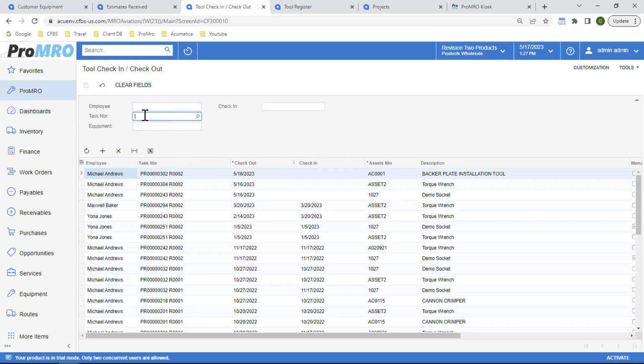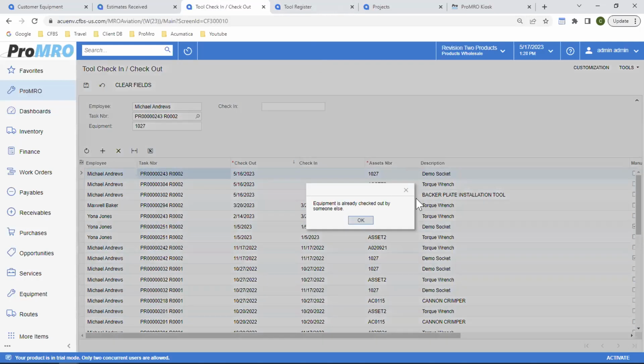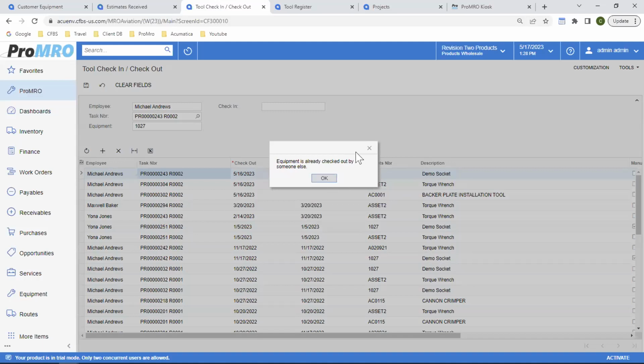I would scan their badge or type it in, and I would also check the unit in. One quick note: if there happens to be a tool already checked out, or it has exceeded its calibration date, meaning the calibration is expired, the system will not allow you to check out that tool. For example, if I am employee 70 and I try to check out this tool, a pop-up box appears, and you can set this as a hard stop or a soft stop, letting you know it's already checked out by someone. It acts the same way for calibration.